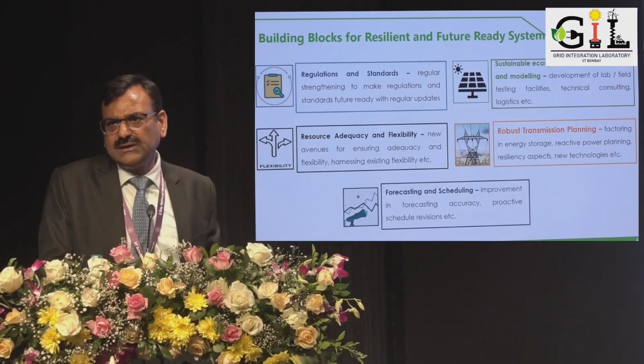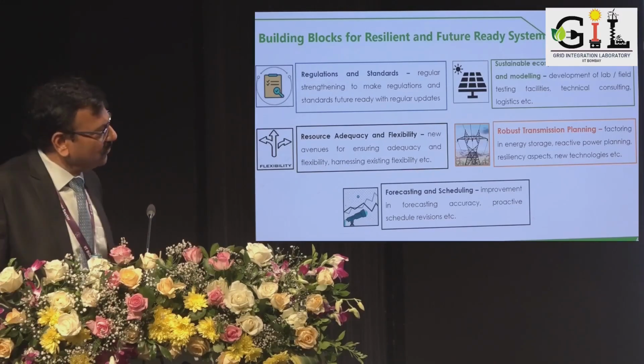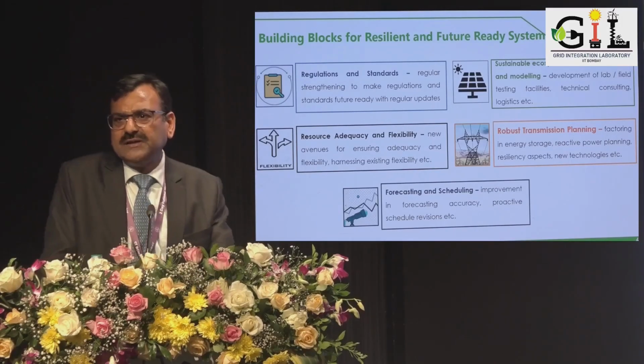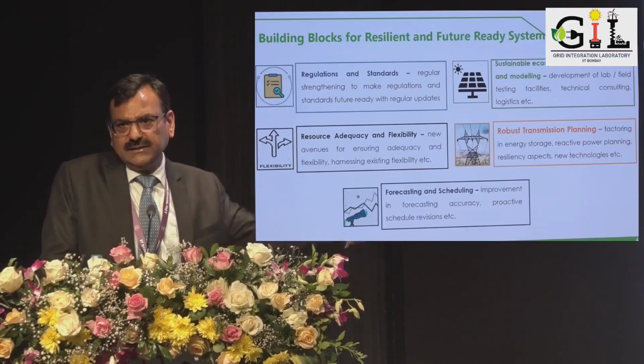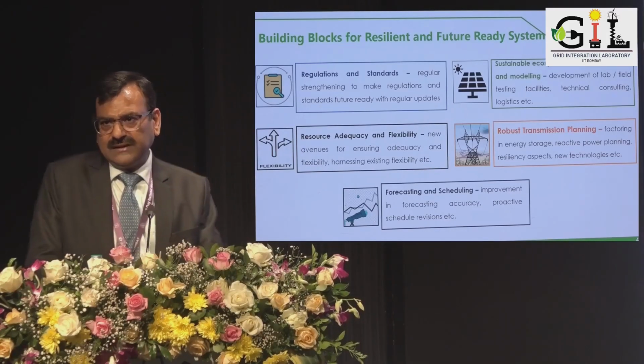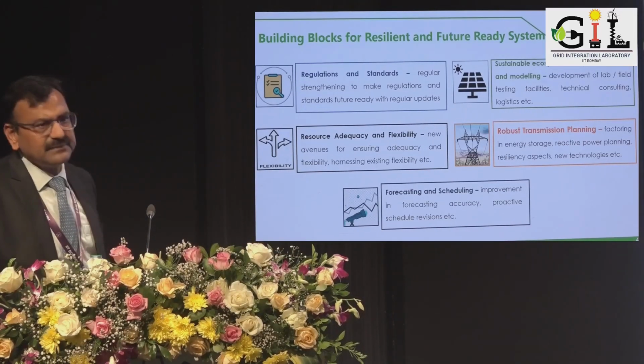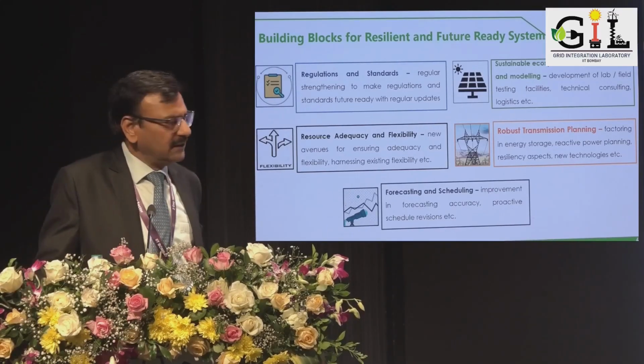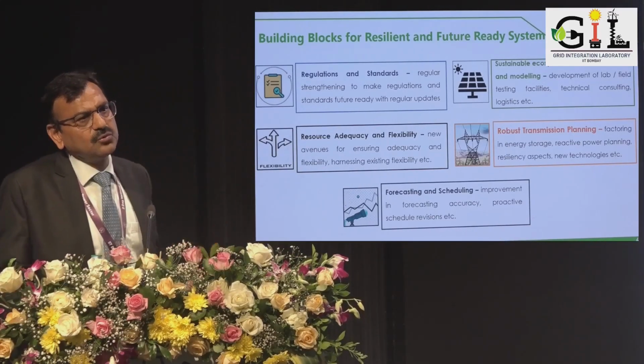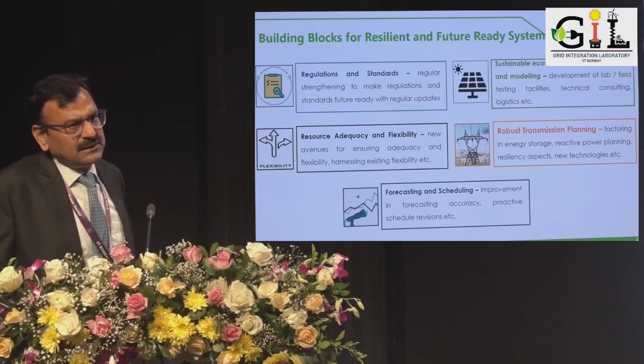It will go into HVRT mode. At high voltage, inverters will go under HVRT, and if they are not properly tuned, we can again have a problem of HVRT and the inverters can trip. This has been happening lately, but with some improvement in settings we have tried to overcome it.